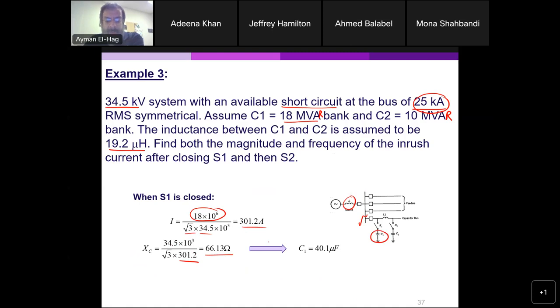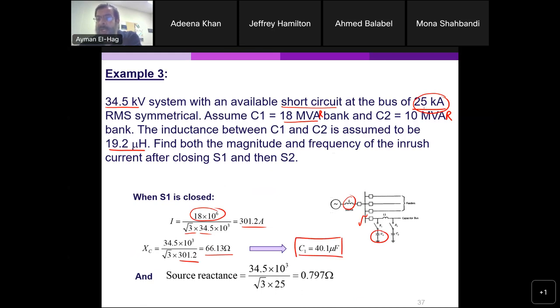Now from this, 1 over omega C is equal to this, so I can find C1. I found C1, the value of C1 is 40.1 microfarad. Now the source reactance, as we mentioned, will limit the short circuit current.